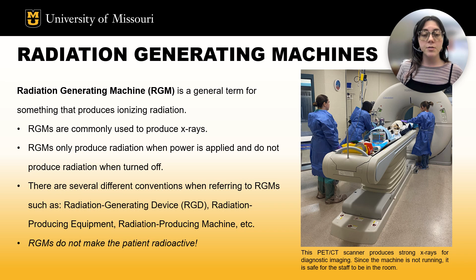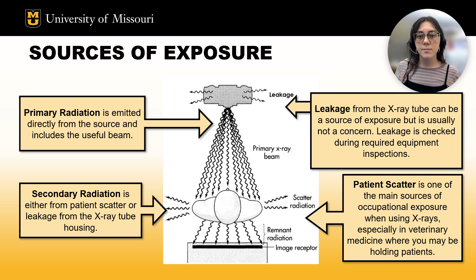When working with RGMs, there are two sources of exposure. The first is from the primary radiation, which is radiation emitted directly from the equipment. The other source of exposure is from secondary radiation. Secondary radiation can be broken down into two types: leakage and patient scatter. Leakage is from the X-ray tube and can occur if there are issues with the tube housing. This is generally not a concern, especially because state-required equipment inspections verify no leakage is occurring. Patient scatter is the other type of secondary radiation. It occurs when the primary beam scatters off the patient. It is the primary source of exposure to X-ray workers in veterinary medicine, especially because vet med workers often have to hold the patients during procedures.